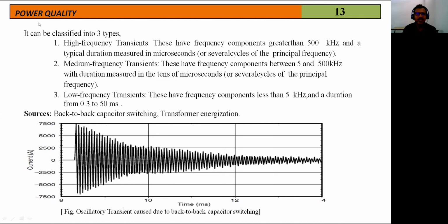The first one is high frequency transients. Second one, medium frequency transients. Third one, low frequency transients. Coming to the high frequency transients, these have frequency components greater than 500 kilohertz and a typical duration measured in microseconds or several cycles of principal frequency. That means the high frequency transients have a frequency greater than 500 kilohertz and a typical duration measured in microseconds. Very small time period, but the frequency is very, very high, 500 kilohertz.